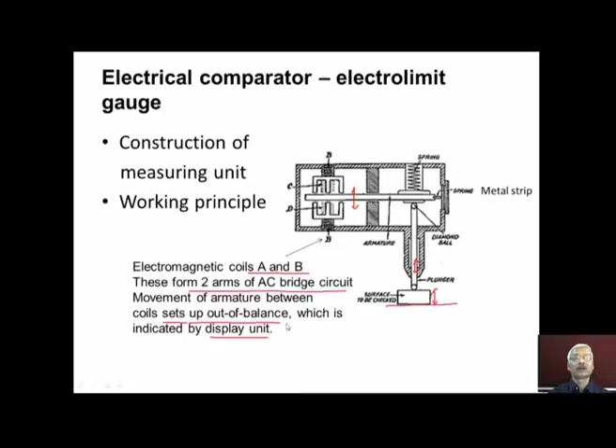Now the plunger movement sets up an out-of-balance condition which is supplied to the recording head. When there is an out-of-balance because of the armature's movement, this pointer will move over the scale, and that movement indicates the deviation of the size from the desired size.